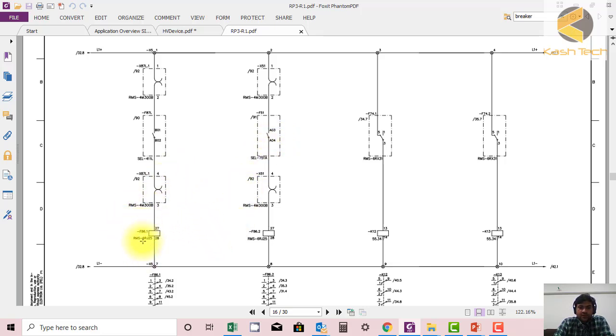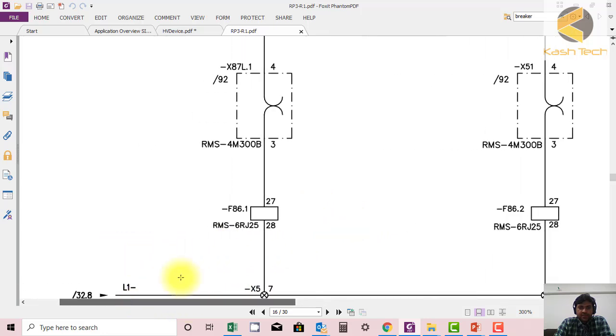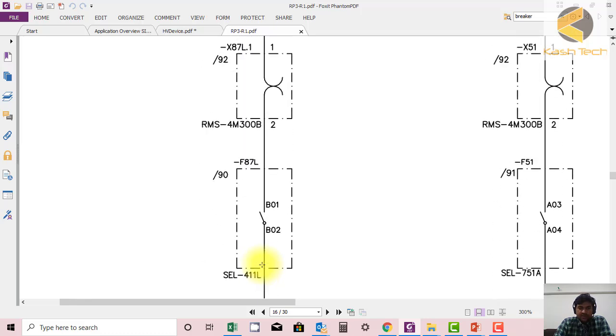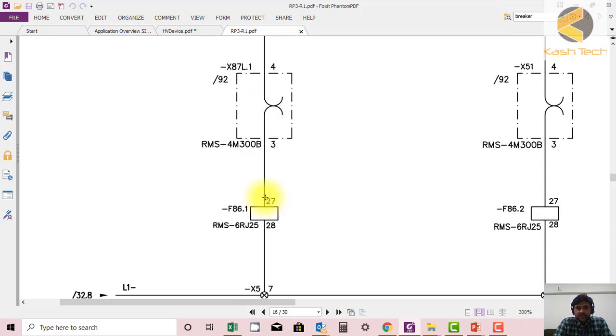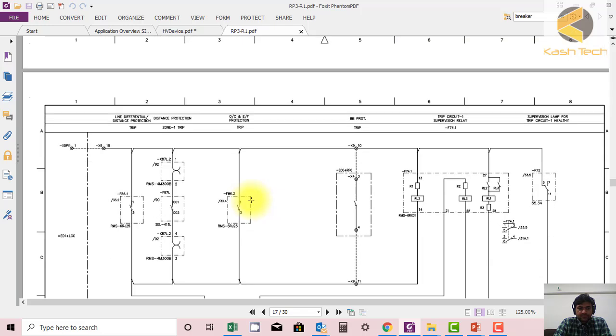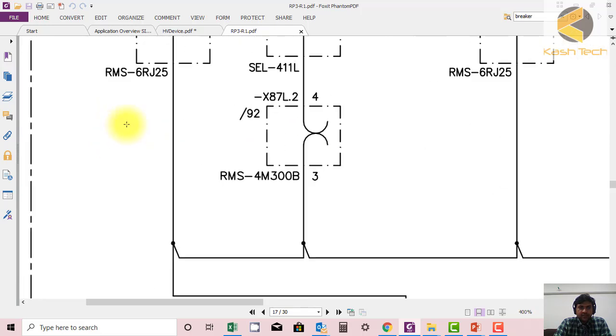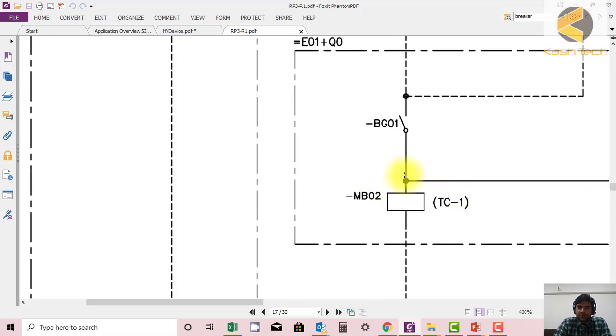Here you can see we have two lockouts on this drawing: page 86.1 and 86.2. Lockout 86.1 is coming into operation through the differential relay — named F87L, where L is for line. It could be T for transformer, or B for bus bar. When this contact is closed, this lockout will operate, and once the lockout operates, the contact of F86 will close and pass DC to the tripping coil.